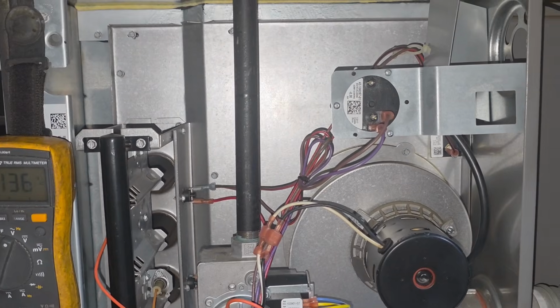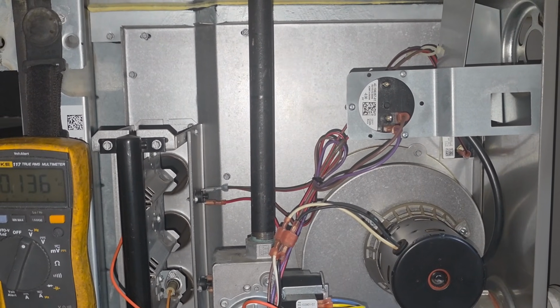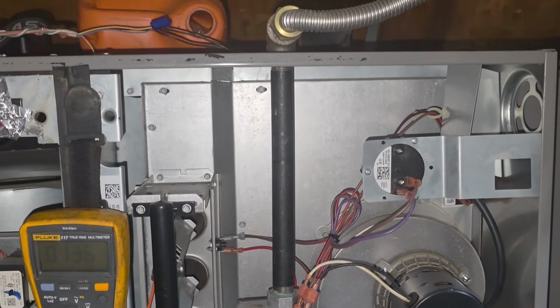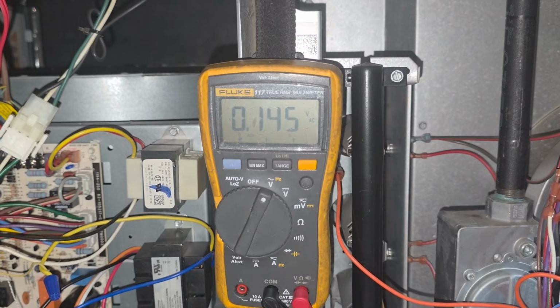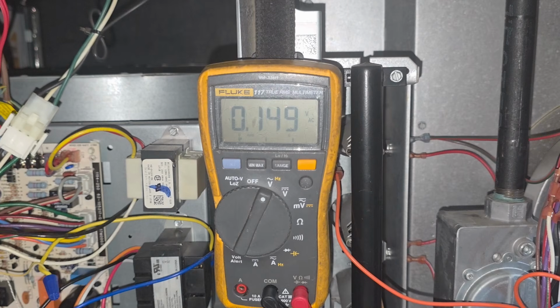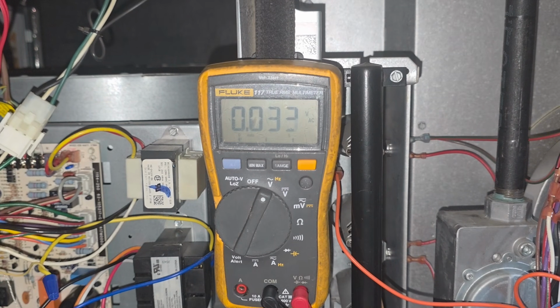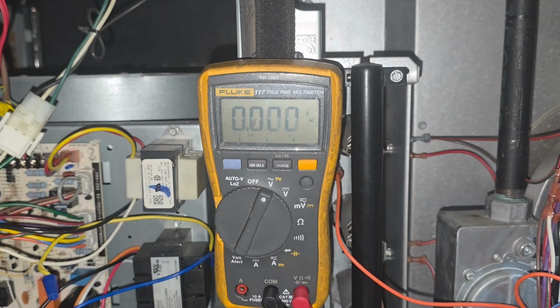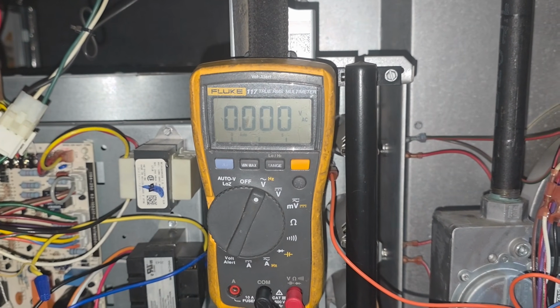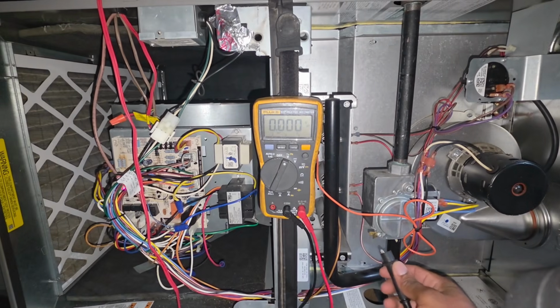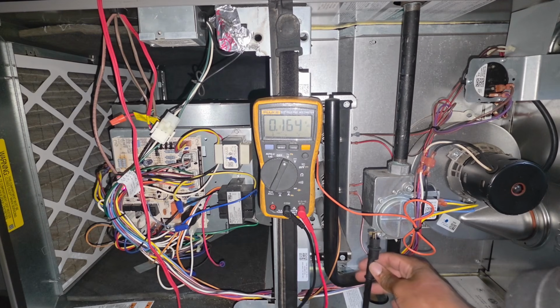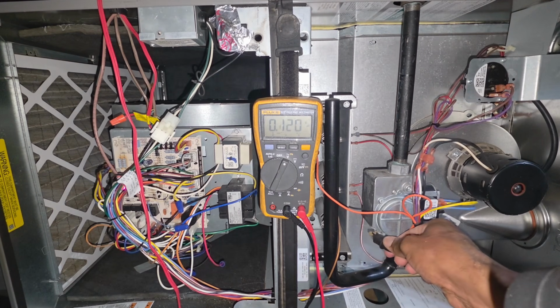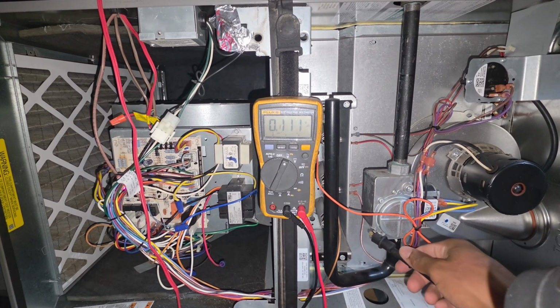All right. Now we want to check some high voltage things. So let me show you how to check the high voltage. So remember, when we're checking these components, you just want to really get you a good ground. I like to use a common ground, but when I'm checking high voltage, I prefer to just give me a good ground instead of the common or the neutral. I just give me a good ground right here.